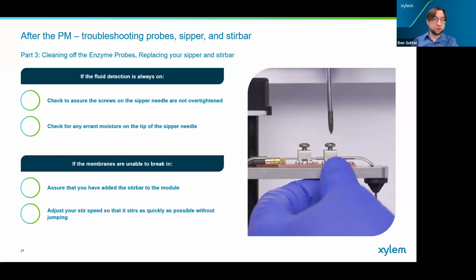You also want to check for any errant moisture. That's typically not an issue, but if you have some sort of media that has a lot of bubbles or foam, it could stick to the end and give you a false positive. Now, if the membranes are unable to break in after you've done all of this, make sure you've added the stir bar. I have seen that very frequently, where the number doesn't change, and that's simply because the stir bar is not in there performing that action and giving us the signal we need. If that does not work, then you may have to adjust your stir speed. In tech support, we always say turn it up as high as you can until it starts jumping all over the place like crazy, and then bump it back a few steps so it slows down. You want it to be fast, but not jumping.